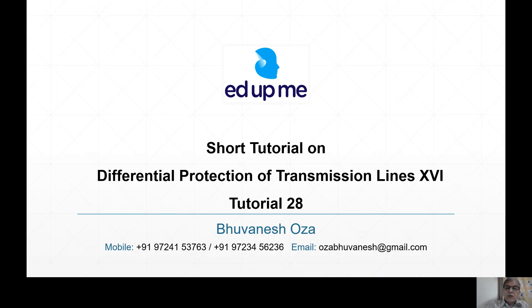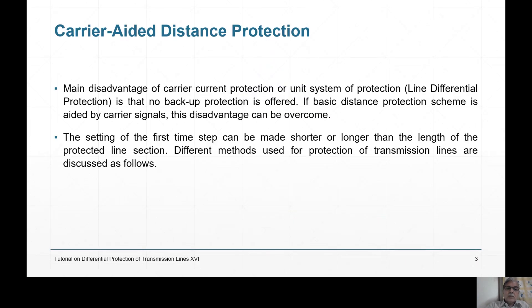In the first Line Differential Protection — the directional comparison scheme we have seen — there was no backup. Here, backup is provided and therefore we will be using basic distance protection. The main disadvantage of carrier current protection as a unit system is there is no backup protection. So if we use a distance protection scheme as a base but aid it by carrier signals, this disadvantage can be overcome.